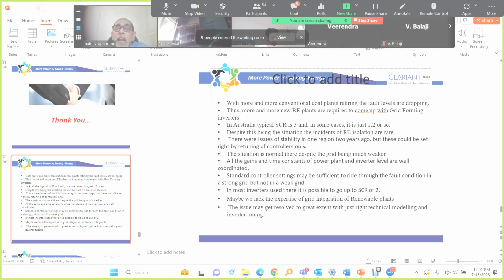You are absolutely right -- SVG or STATCOM will only work in a steady state condition under the present scenario. If you don't have those loops and things, even capacitors will work in steady state, so why have a STATCOM? That is what I am questioning these people -- STATCOM can give dynamic control during steady state, but during a fault condition, if the fault is beyond its capability, it is not going to do anything.